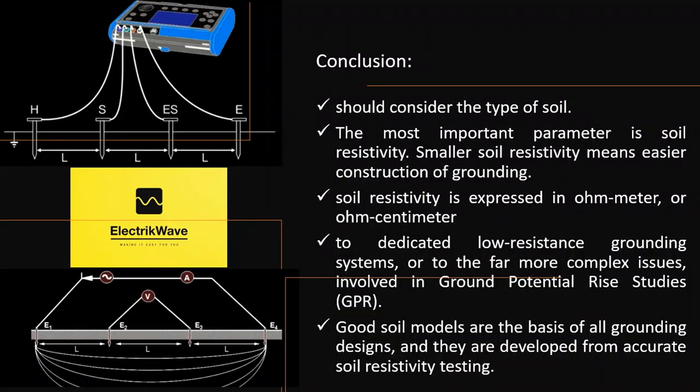Conclusion: Designing earth ground systems should consider the type of soil. The most important parameter is soil resistivity. Smaller soil resistivity means easier construction of grounding which fulfills the requirements. Soil resistivity testing is the process of measuring a volume of soil to determine the conductivity of the soil. The resulting soil resistivity is expressed in ohm-meter or ohm-centimeter. Soil resistivity testing is the single most critical factor in electrical grounding design — true when discussing simple electrical design, dedicated low resistance grounding systems, or the far more complex issues involved in ground potential rise (GPR) studies. Good soil models are the basis of all grounding designs and they are developed from accurate soil resistivity testing.